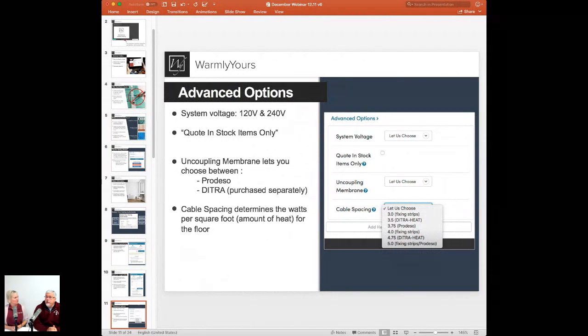And also, if you're in Illinois and it's really, really cold, you would use the 3-inch spacing downstairs in the basement, and you could maybe use the 4-inch spacing upstairs in the bathroom floor because there's already a warm floor below it because it's above a kitchen. Brilliant. And the great thing about this tool is you can run it several different ways to figure out which you like best. And that'll keep you at a cost. It'll keep you below a certain amount of power. So that's a great way to just play around with this different spacing.